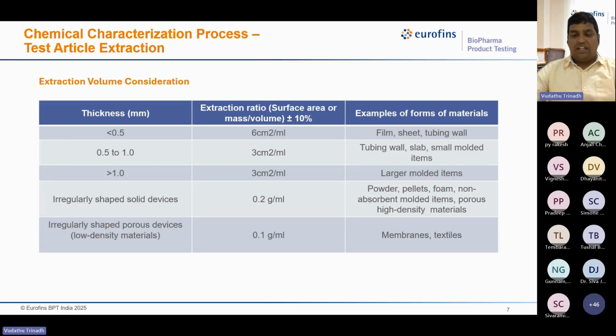Say, suppose these are examples for membranes and textiles. If your medical device is an absorbable medical device, then you have to test in such a way how much volume has been absorbed, or how much volume of extraction solvent can be absorbed. You have to measure before initiation, and the same volume will be measured and added to the extraction volume during extraction studies.